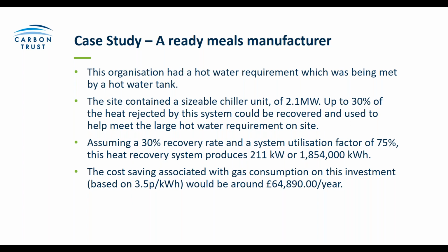But because of the size of the chiller unit they had for their line of work, we were able to identify and recommend to them that up to 30% of that heat that was originally rejected by the system could actually be recovered. And it could be used to meet the demand for hot water on site.